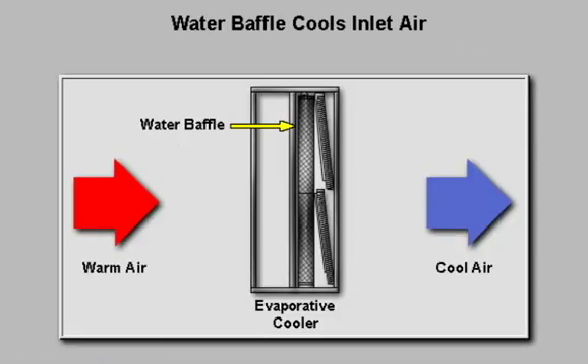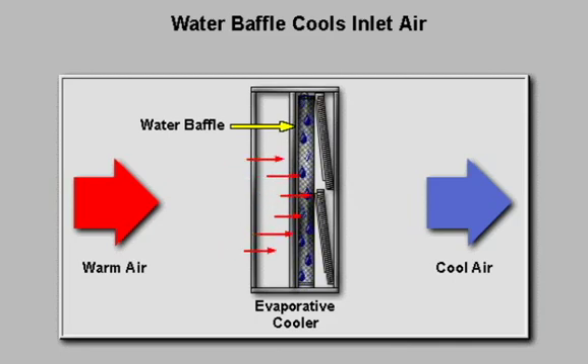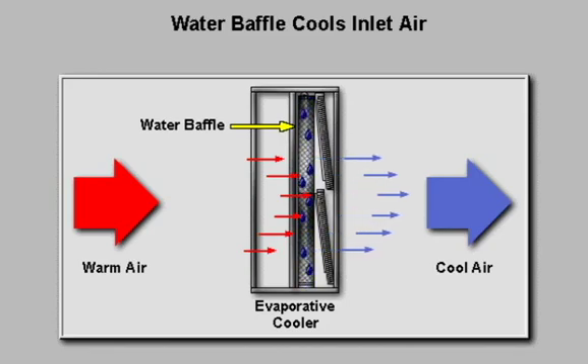The primary component of an evaporative cooler is a water baffle. Water is distributed over the top of the baffle and flows downward through the baffle media. Inlet air flowing perpendicular to the water flow evaporates some of the water. This cools the inlet air and increases its density, which in turn improves the power output of the turbine.